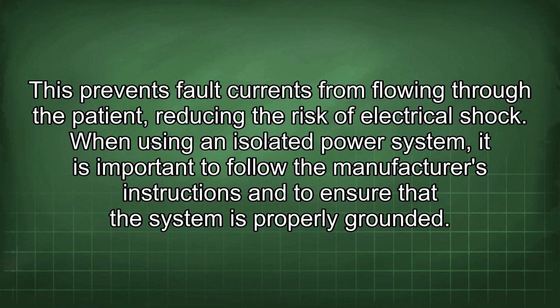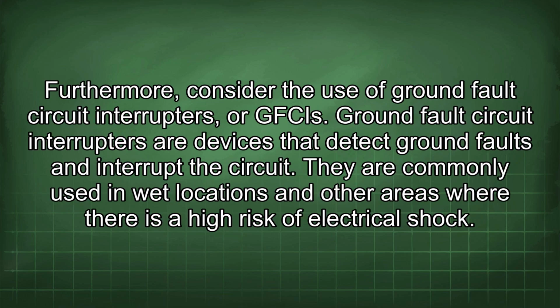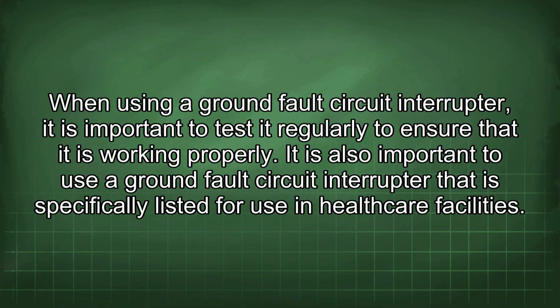When using an isolated power system, it is important to follow the manufacturer's instructions and to ensure that the system is properly grounded. Furthermore, consider the use of ground fault circuit interrupters, or GFCIs. Ground fault circuit interrupters are devices that detect ground faults and interrupt the circuit. They are commonly used in wet locations and other areas where there is a high risk of electrical shock. When using a ground fault circuit interrupter, it is important to test it regularly to ensure that it is working properly.